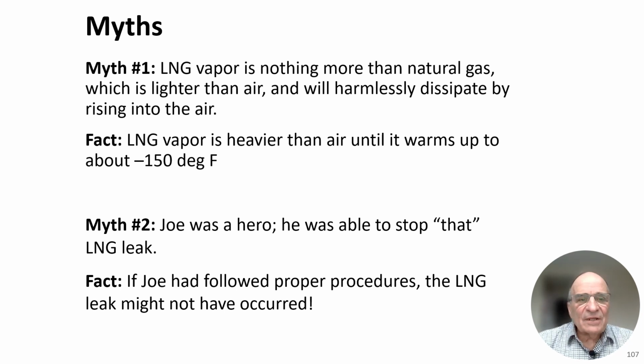Myths are a common concern in LNG facilities. Myth number one: LNG vapor is nothing more than natural gas, which is lighter than air, which will harmlessly dissipate by rising into the air. And that's typically what PR people will say about boil-off gas. However, it is known that LNG vapor is heavier than air until it warms up to about minus 150 degrees Fahrenheit.